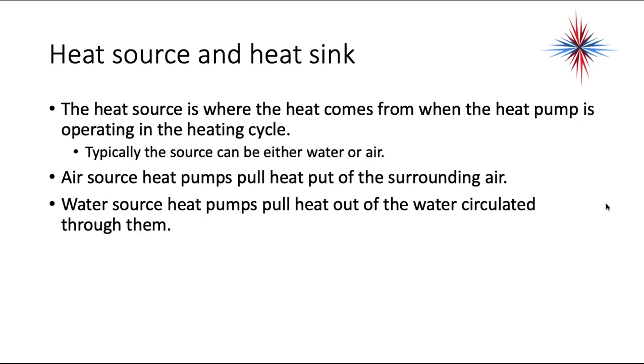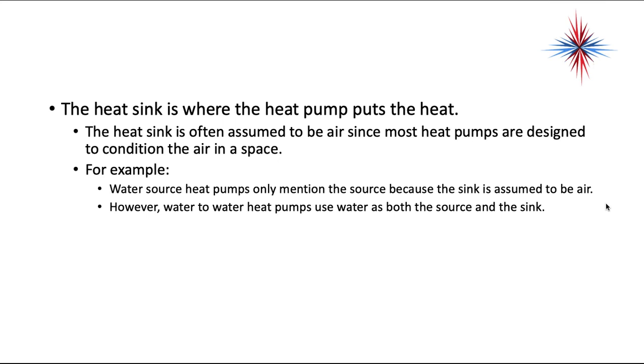There are 2 other terms we have to talk about. I already mentioned them once: heat source and heat sink. The heat source is where the heat comes from when the heat pump is operating in the heating cycle. Typically, the source can be either water or air. Air source heat pumps pull heat out of the surrounding air. Water source heat pumps pull heat out of the water circulated through them. The heat sink is where the heat pump puts the heat. The heat sink is often assumed to be air since most heat pumps are designed to condition the air in a space. Water source heat pumps only mention the source because the sink is assumed to be air. That would be geothermal type heat pumps. However, water-to-water heat pumps use water as both the source and the sink. But notice that water-to-water is actually named.